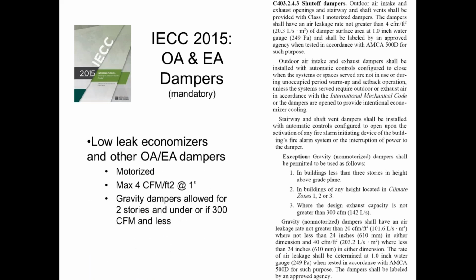Additionally, all outside air dampers need to be motorized, and they need to be rated as low leak dampers per AMCA 500D standard. There are exceptions where the damper does not have to be motorized, but we're not going to talk about those today because on a rooftop unit, as soon as I go to an economizer, it has a motor, so I'm automatically in the motorized area. So hence, all economizers in Illinois, irregardless of size, need to be low leak dampers. So if I put a 2-ton rooftop on a unit, I'm not required to have an economizer by code, but I am required to have an outside air shutoff damper, and if it's motorized, it's going to have to be this low leak scenario. So if you put a 2-ton rooftop unit on with an optional economizer not required by code, you still have to do what's on the screen here. So all economizers need to be low leak dampers.